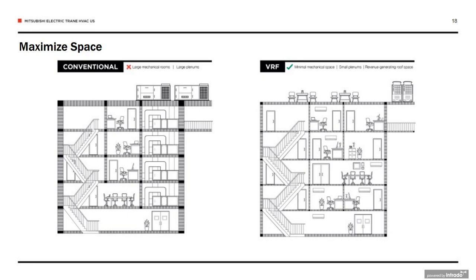An example where we remove the mechanical room: the VRF can give you back valuable space that can be used to generate income. Here you see the two side by side, with the conventional system on the left and the VRF on the right. As you can compare, the extra space from that mechanical room can now be used for an additional office or can be used as leasable space. This allows for amenities the tenants will enjoy. Typically, you're going to add a rooftop bar, maybe some green space, which is going to be highly desirable for the way that we move forward in office application.